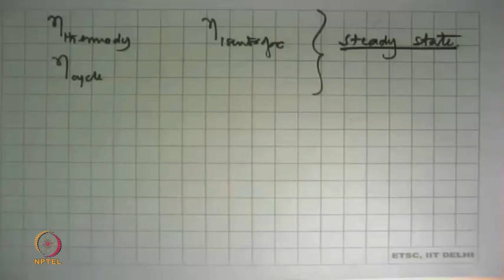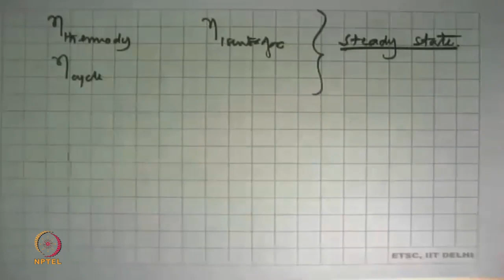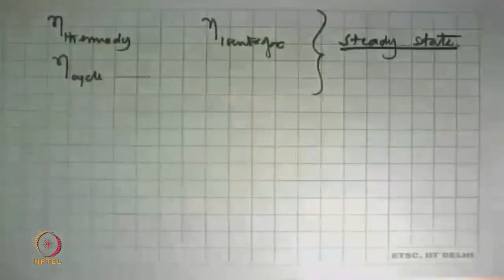You need a very, very well designed, well controlled environment which costs 100 crore rupees, and it takes a lot of money to actually do one test. And that's the only test which actually makes sense. The same thing is the case of an operating power plant, where throughout the day the ambient temperature keeps going up and down, and how will you get steady state when the temperature of air going in keeps changing all the time? It's very, very difficult to make measurements. You have to make special test chambers in which we can do that, and those are well documented in various processes and standards with which you can measure the efficiency of these devices.